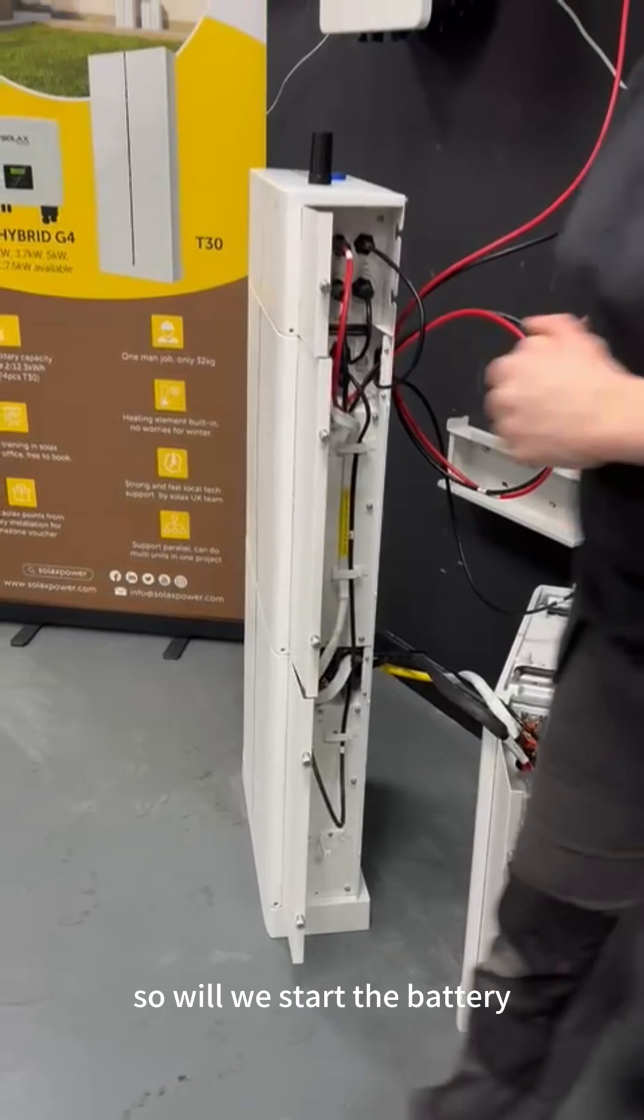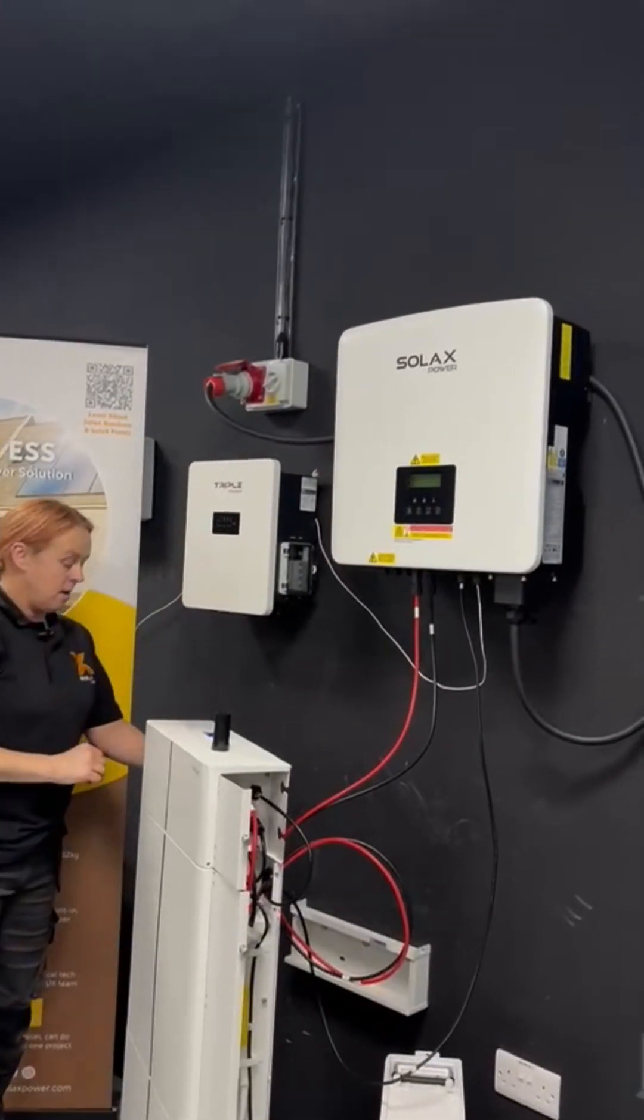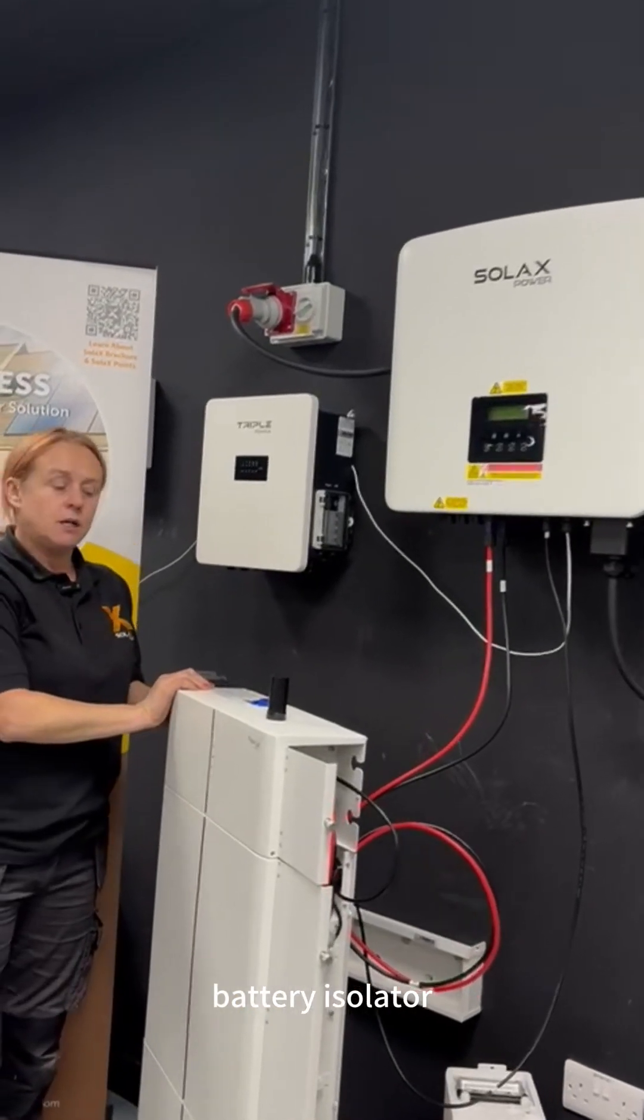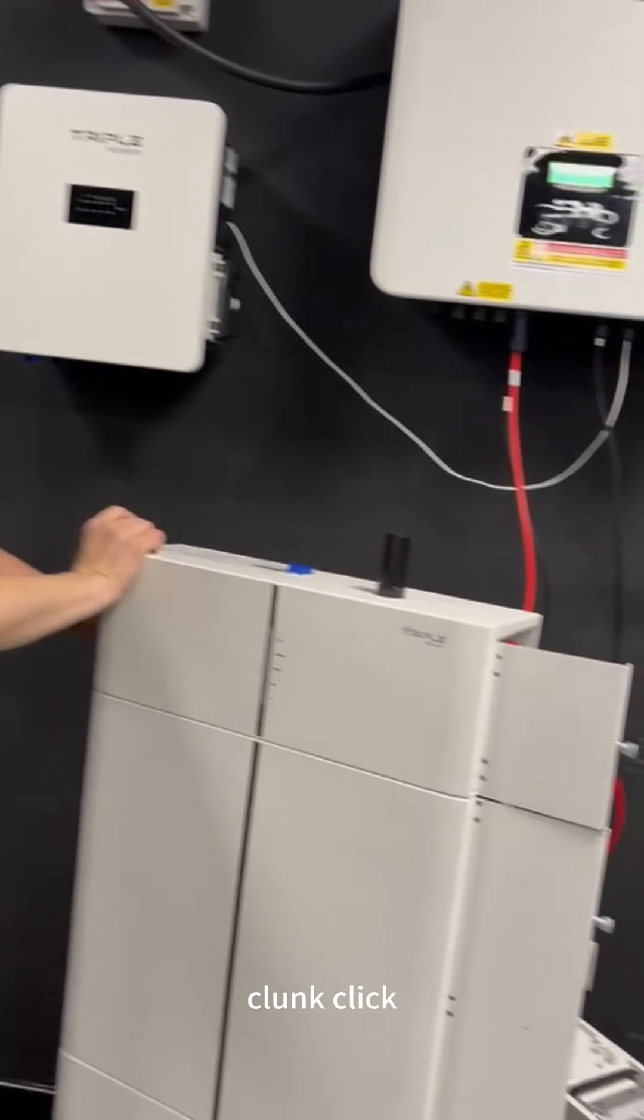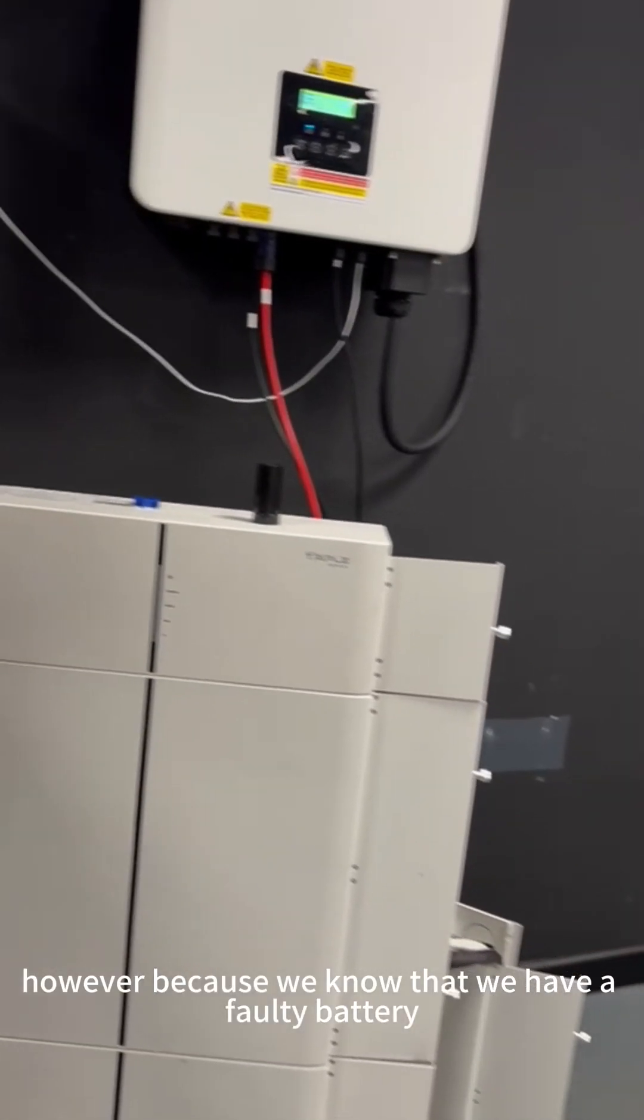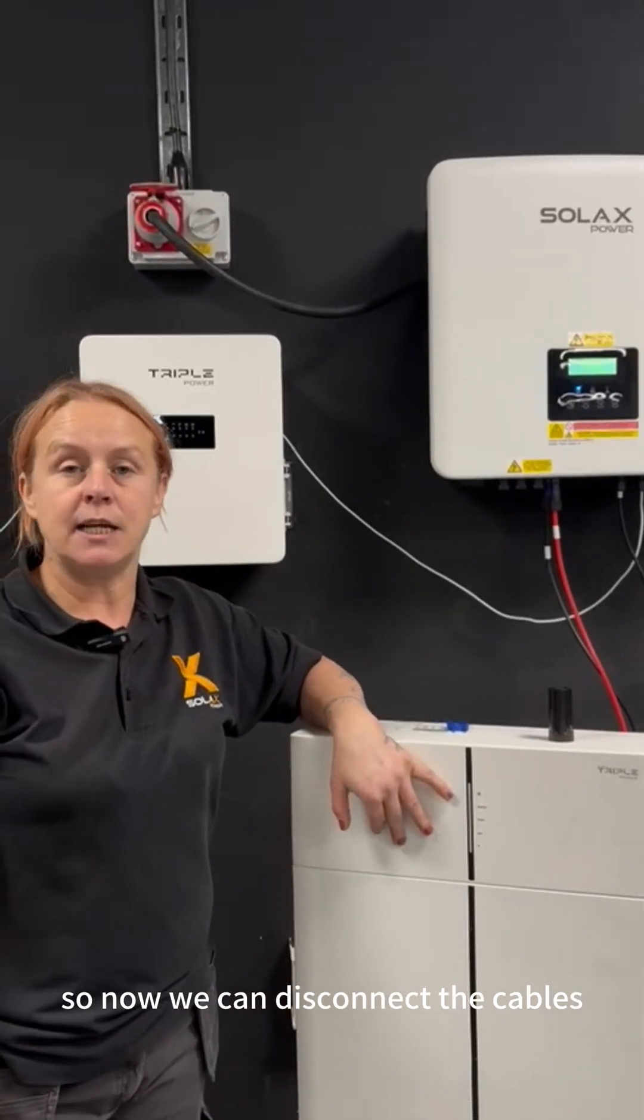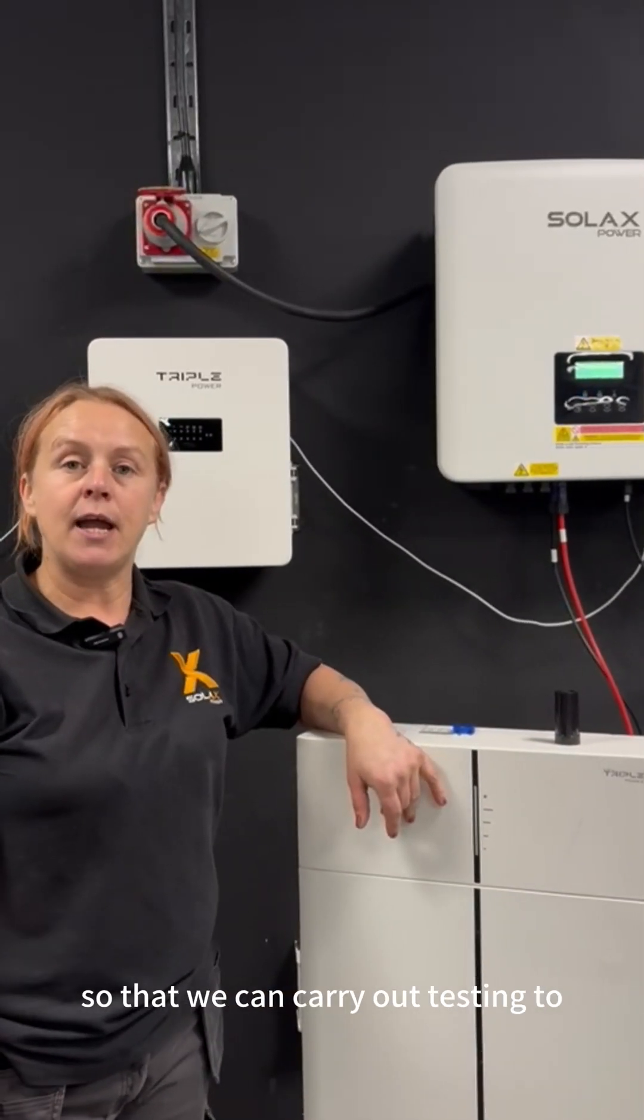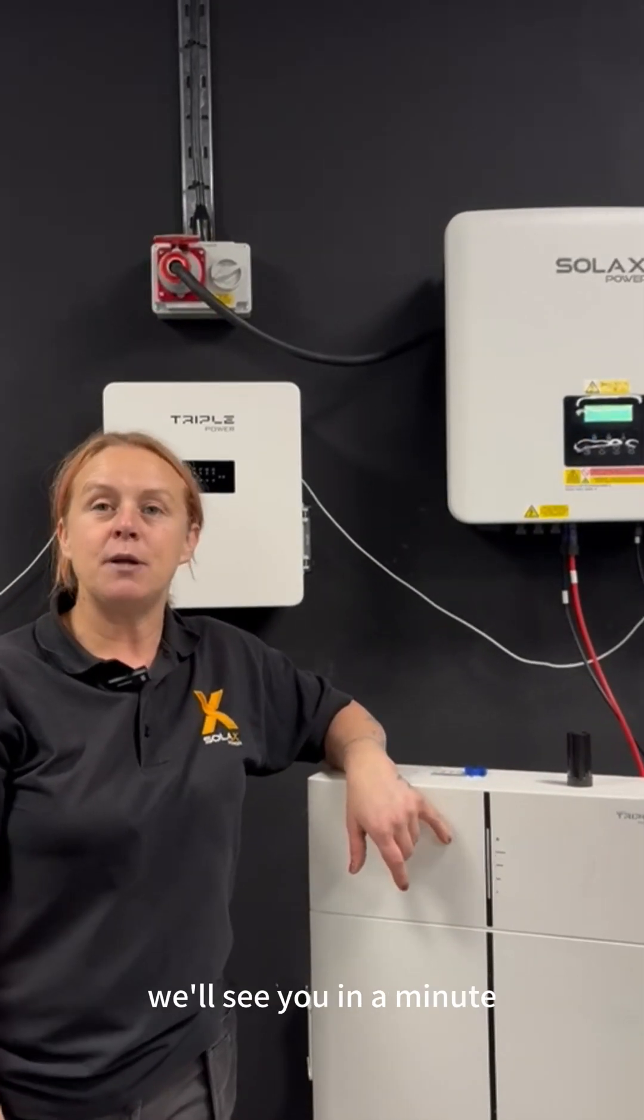So we'll restart the battery and the inverter first. Battery isolator, button, clunk, click. However, because we know that we have a faulty battery in the system, our lights are not going to come on. So now we can disconnect the cables so that we can carry out testing to verify which one of our batteries is faulty.